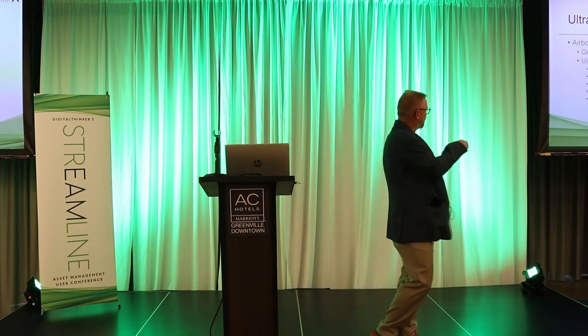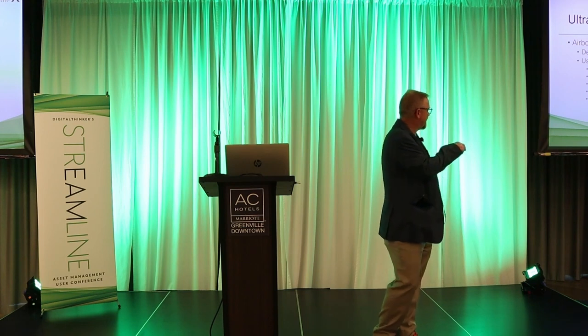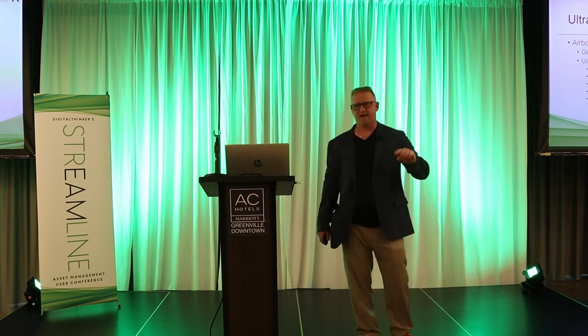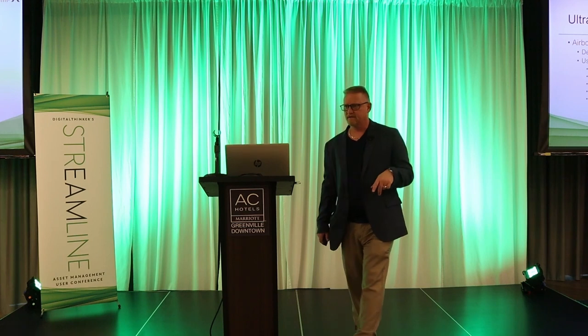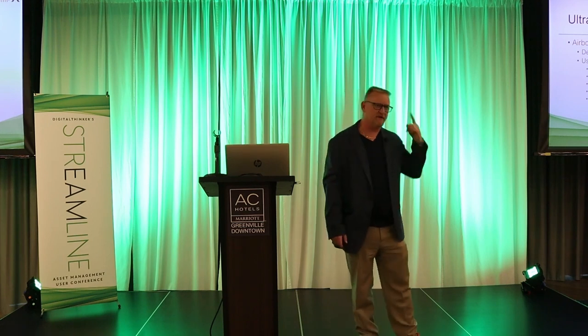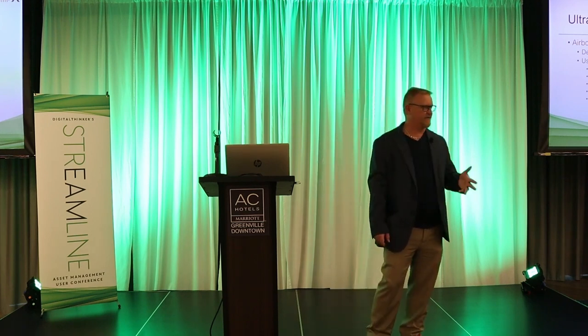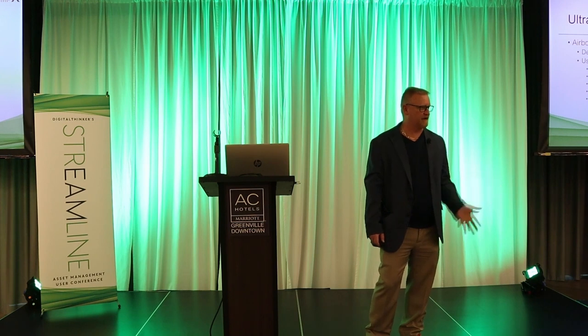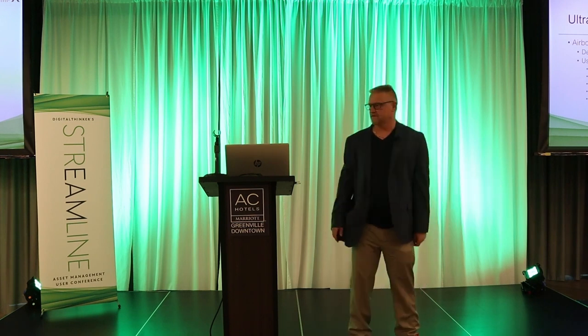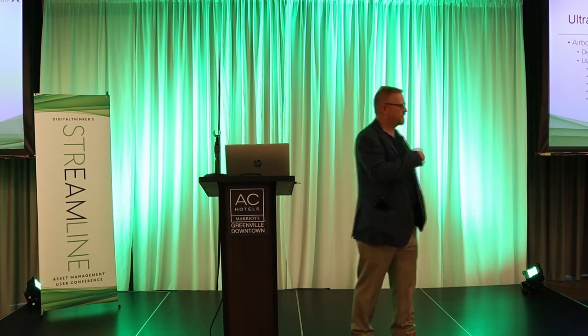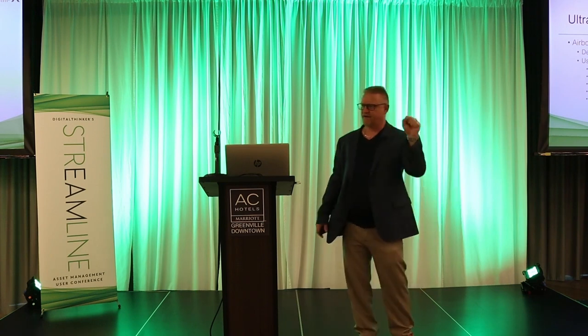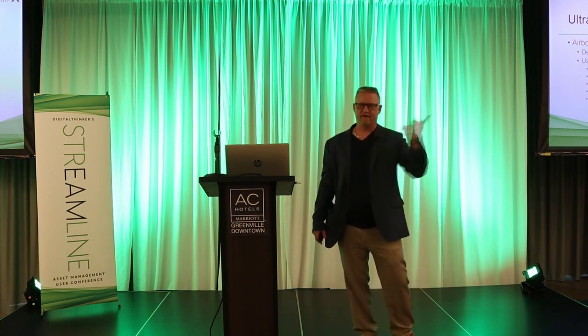So in an airborne scenario, it looks for gas leaks, vacuum leaks. It can also pick up electrical corona, arcing, without having to remove the cabinet because it's audible. So you don't have to open up the cabinet to hear arcing or corona. Also good for tank inspections. They have a tone generator. You drop it in the tank, close the tank, you can hear any leaks.